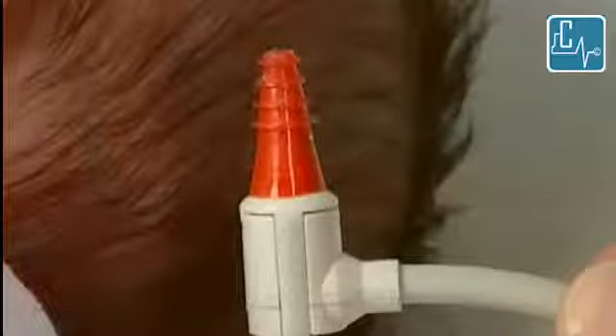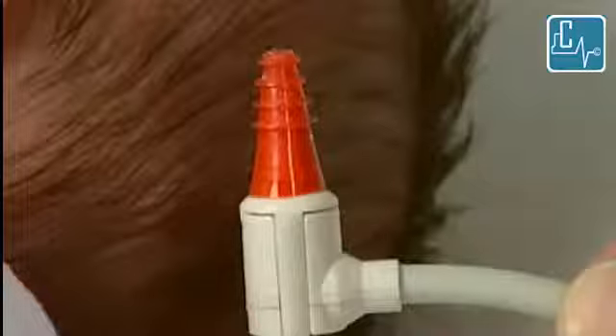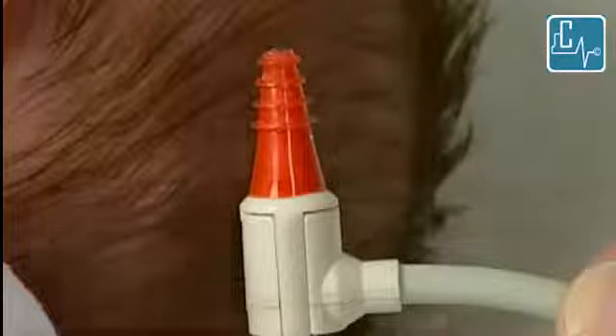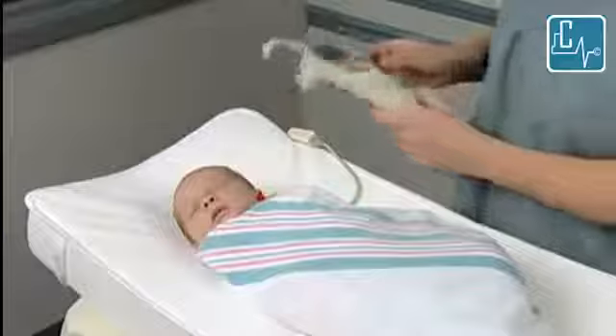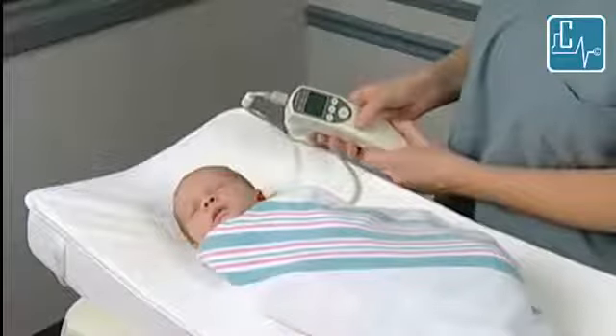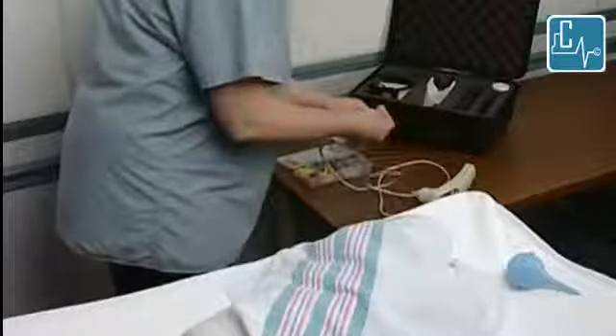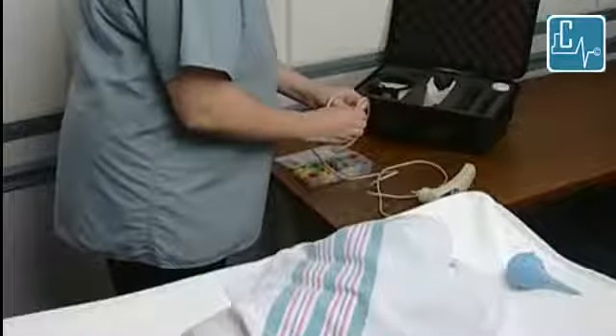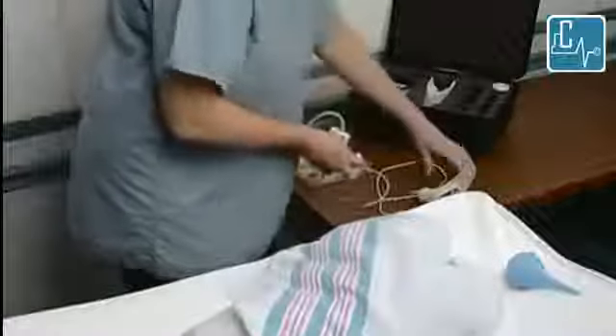When screening an infant with the external probe, the red flanged ear tip is usually the best choice. This is because the tip makes a better seal in the ear canal when your hand is not there to assist. To begin testing a newborn, select an ear tip. Place the ear tip as far down as possible on the probe tip.